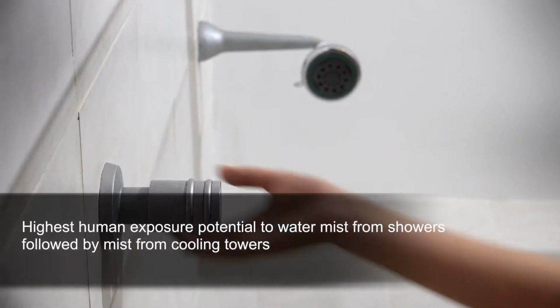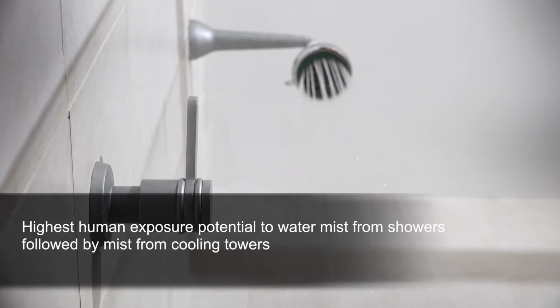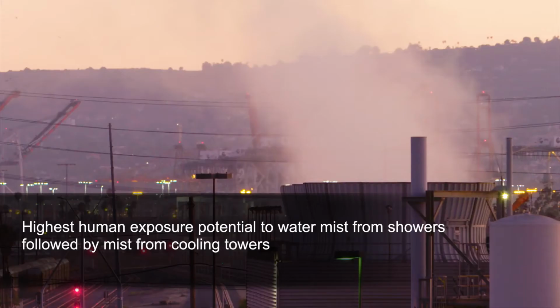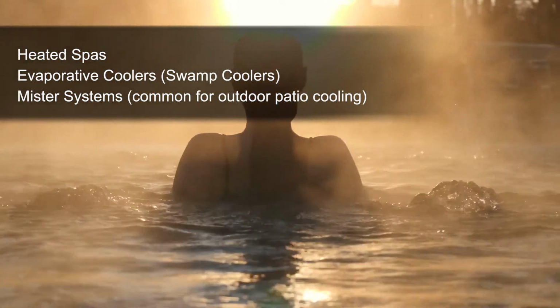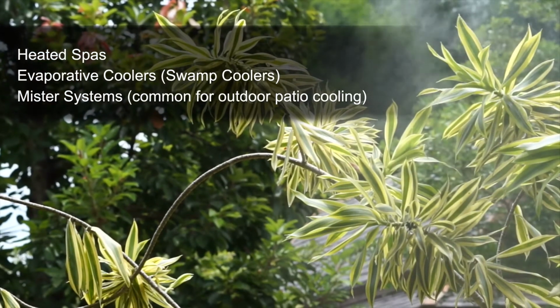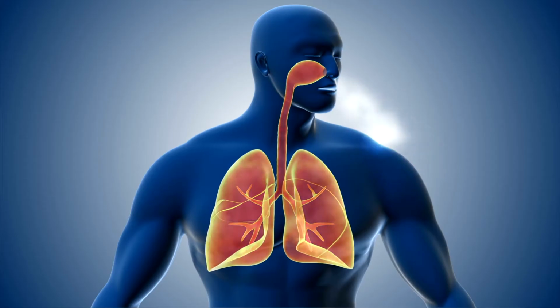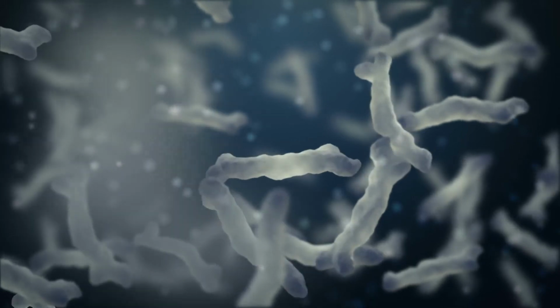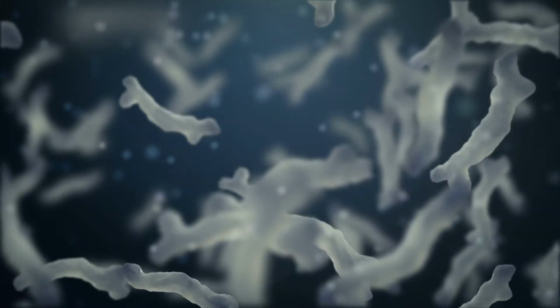Well, let's talk about in your built environment, where are water mists generated? Number one, the shower. This is the number one source of exposure. Number two might be cooling towers, particularly in environments where people are leaving windows open or spending time next to cooling towers, like the smoking section. Heated spas, evaporative coolers, mister systems. These are all very common pathways for the generation of mist and then the potential for the inhalation of mist that may contain Legionella disease bacteria.